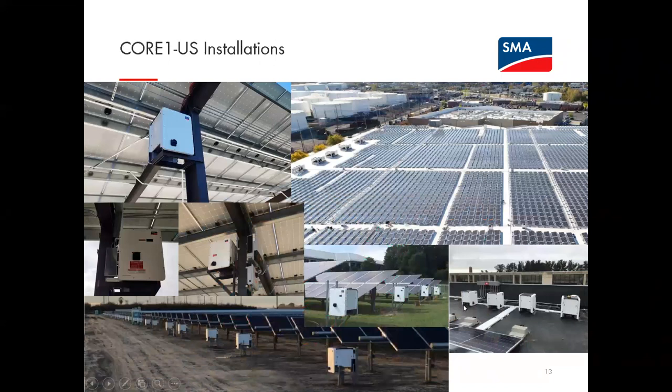We include four EPDM commercial rooftop feet with each device for the ability to be freestanding. Obviously, say out in California, there would likely be seismic requirements that would require the inverters to be anchored somehow, and that's certainly possible to have a roof penetration that can then be leashed or tethered or attached via a rigid device to one of the threaded screw holes in the body. But otherwise, they may be able to use for maximum support the four commercial roof feet.